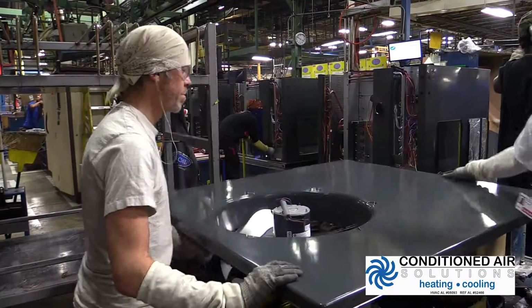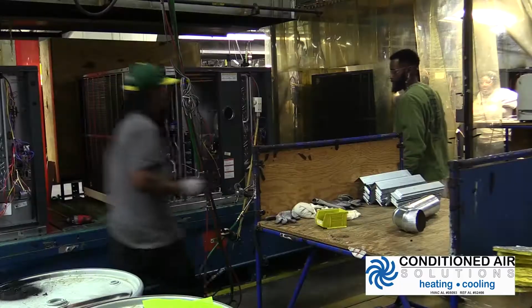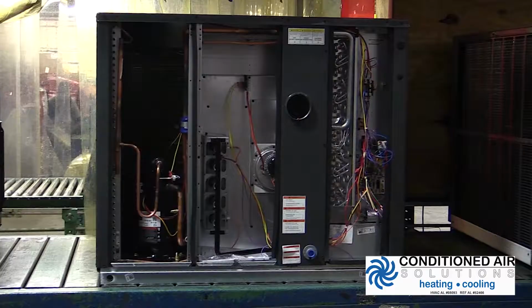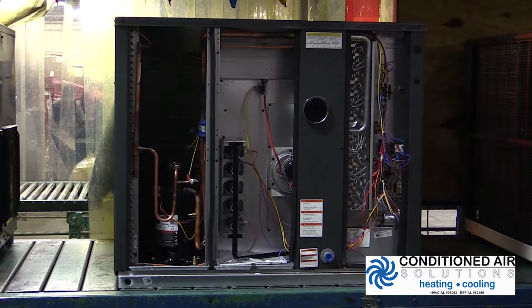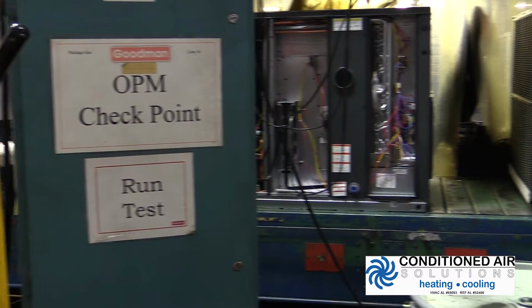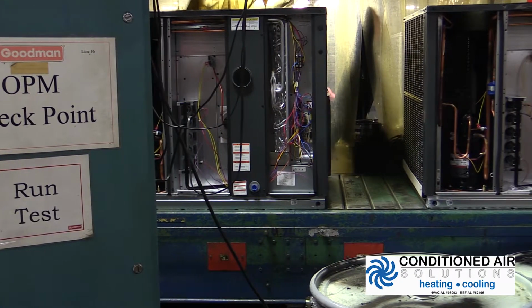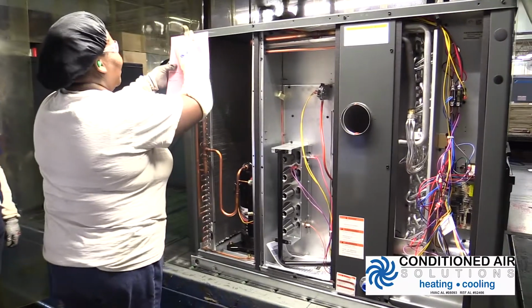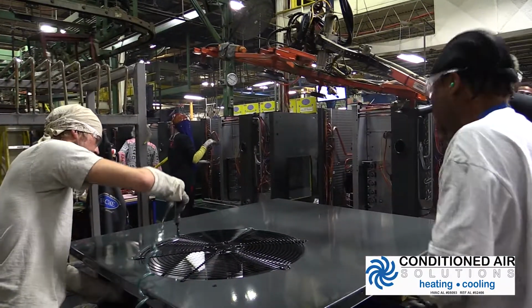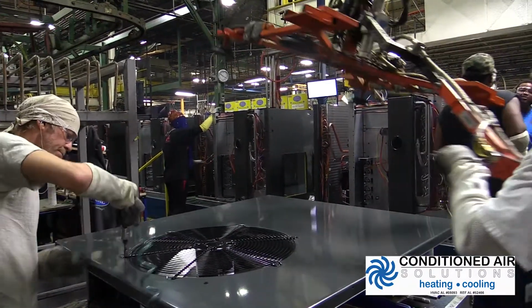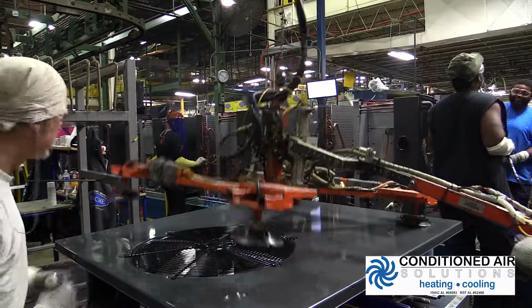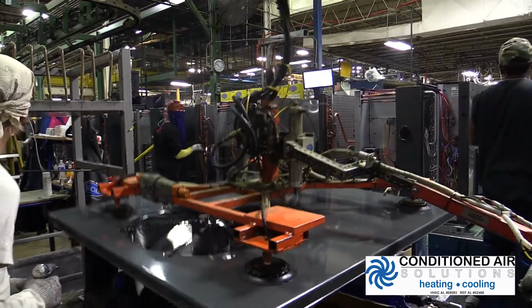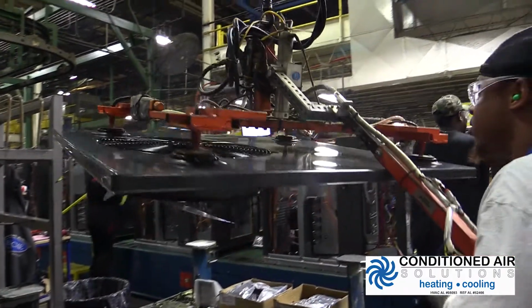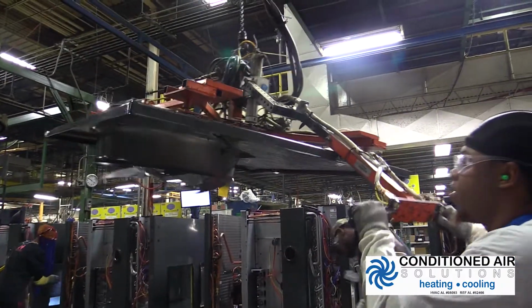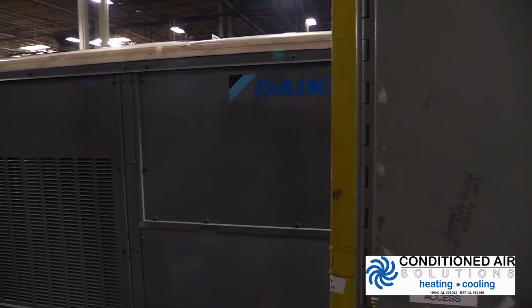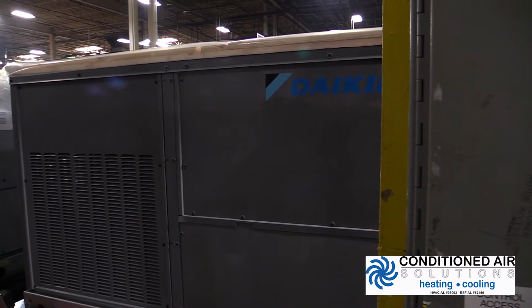As the sealing of the system nears completion, it is pressurized to make sure it will not leak during operation. The now sealed refrigerant system is evacuated to remove all byproducts of assembly, air, moisture, and to prove the system is fully sealed. The top assembly is installed with supporting structure components to start the cooling and heating final testing. All heating components are tested through the run cycle as well. We have actually been testing a stainless steel unit at our Fayetteville facility for several years, and it is still running strong. It's quality that works.